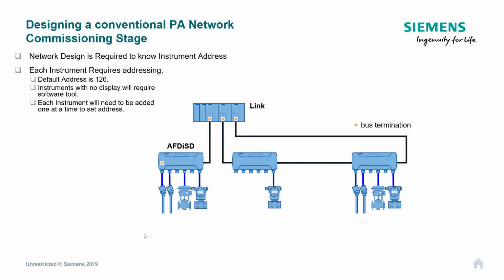During the commissioning stage, we have to program the instruments, and we also need to set the address of the instruments. Now that is nice and easy if the instruments have got displays or dip switches, as long as you can get to the instruments. We know that during the commissioning stage, for instance, if you've got a level radar, you might not be able to go on top of the tank yet, but it's all wired up. So you can use tools. PDM is one of the tools that you can use.